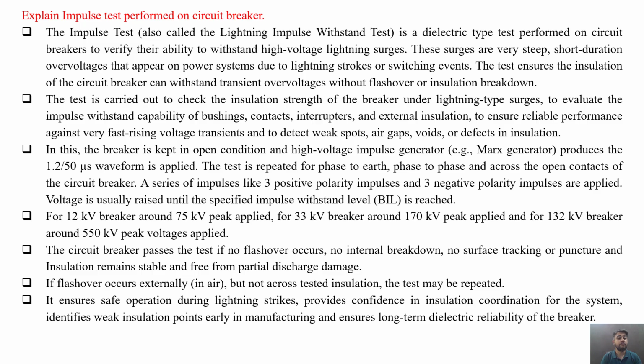is applied. The circuit breaker passes the test if no flashover occurs, no internal breakdown is noticed, no surface tracking or punctures, and the insulation remains stable and free from partial discharge damage. If the flashover occurs externally, that is in the air but not across the tested insulation, the test may be repeated again. It ensures safe operation during lightning strikes.